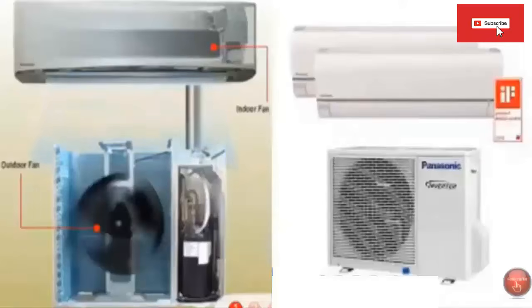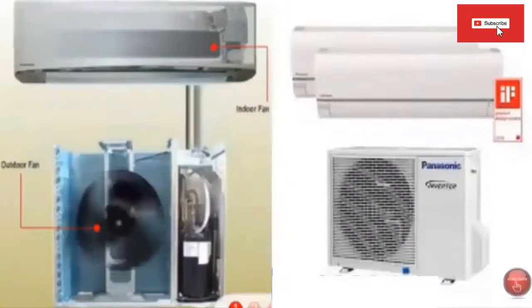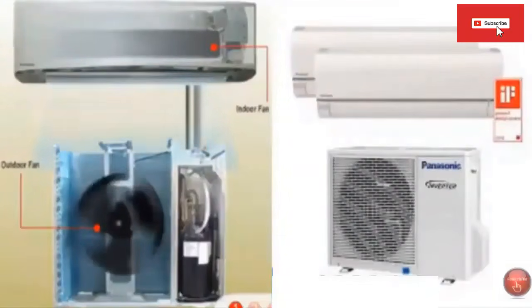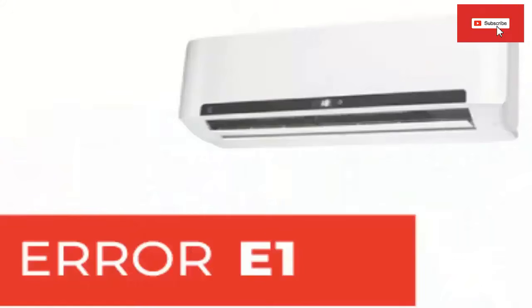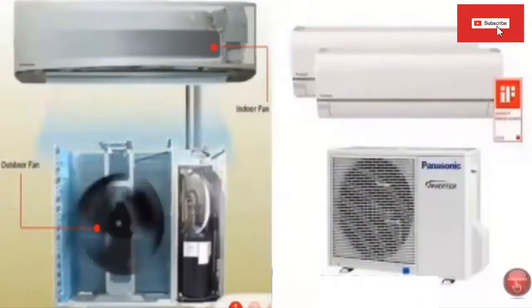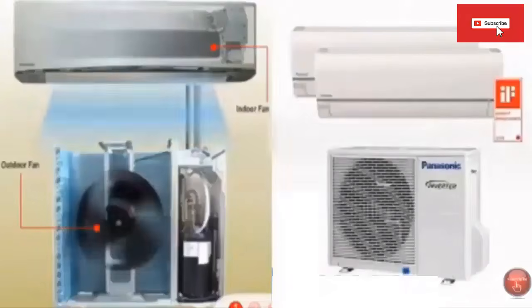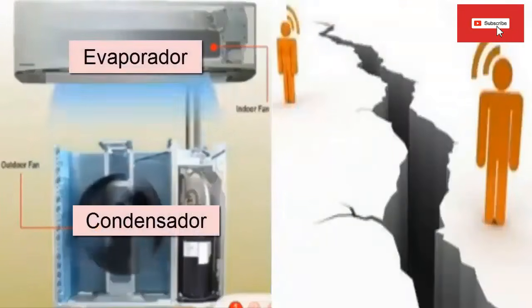Error code 1 is a common error code that can appear on air conditioners of all makes and models. The one error code in the air conditioner can have different meanings, which depend on the manufacturer of the equipment. However, for most manufacturers, error 1 in air conditioning indicates a problem with communication between the indoor evaporator and outdoor condenser units.